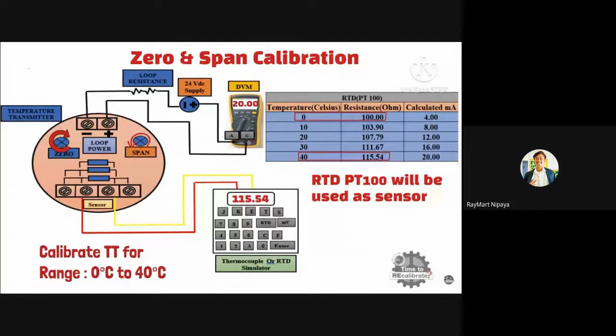First of all, apply 100 ohm resistance value to the transmitter, and check the value in the DVM. The measured value should be 4 milliamperes. After this, apply 103.90 ohm resistance value to the transmitter, and check the value in the DVM. The measured value should be 8 milliamperes. After this, apply 107.79 ohm resistance value to the transmitter, and check the value in the DVM. The measured value should be 12 milliamperes.